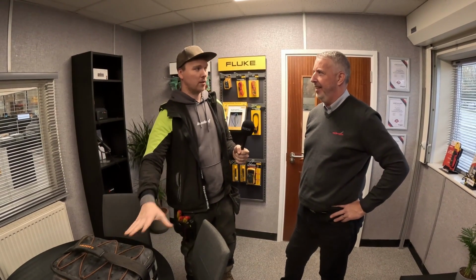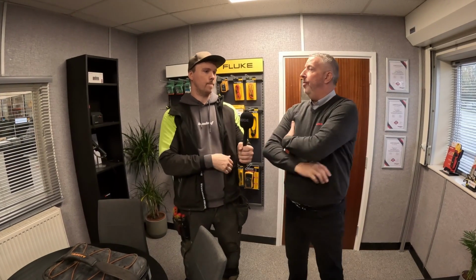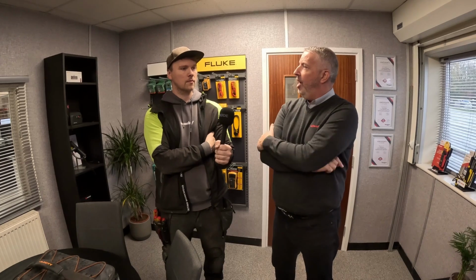Right, got a Megger, a few questions I want to ask you to start with. Calibration centre - what is the reason we need to get our testers calibrated? To ensure the accuracy, really, every 12 months. So manufacturers state to check the instruments every 12 months to make sure that they're still within spec.